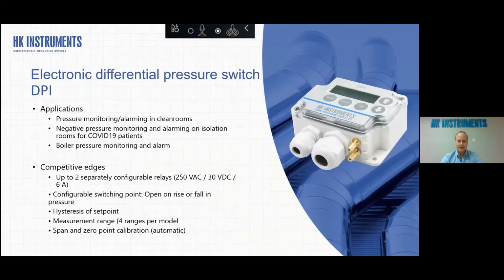Then we have this DPI, the pressure switch, and the applications are, as said before, the clean rooms by controlling some alarms or beacon lights. And then I read an article from Rehva just a moment ago that they are suggesting this kind of instrument for the patient rooms for COVID patients that have been isolated. And there was mentioned that they should maintain at least 5 Pascal under pressure in the isolation room. And if there comes some leakage or something happens in the ventilation, they should have an alarm from that.